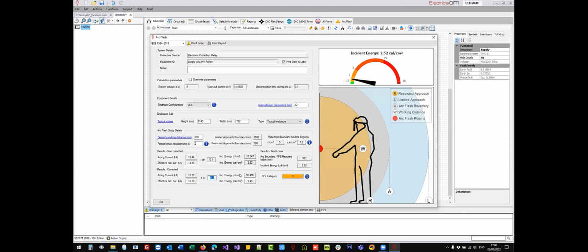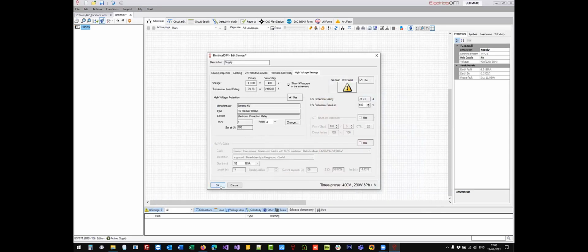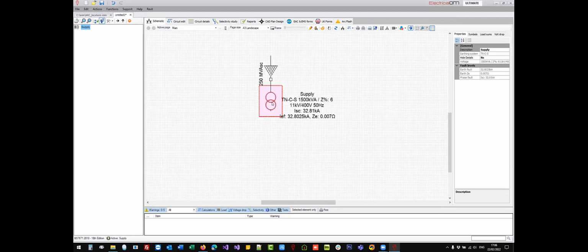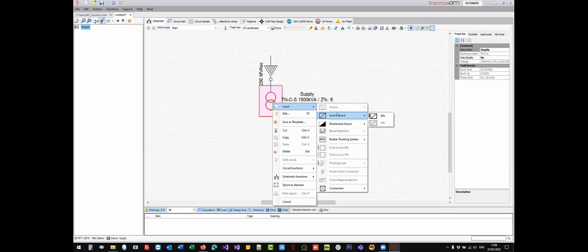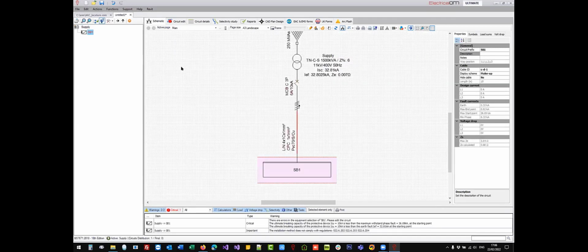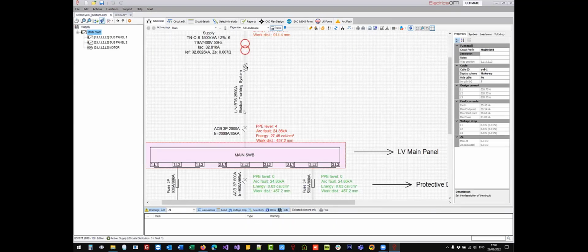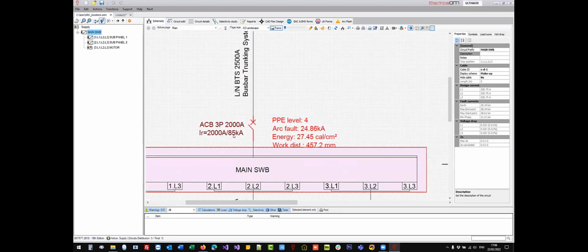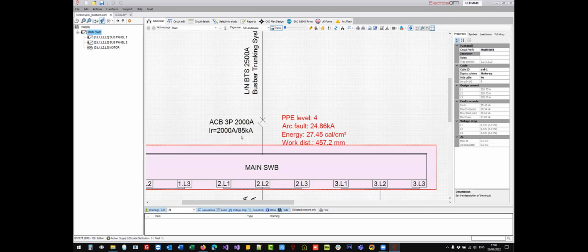Okay, so we can see that there is a direct link between the settings of the device and, of course, the result of the incident energy to be considered. Now, I will OK this to accept all these changes, and then I will move on to inserting my main panel. So I'm right-clicking the source, insert switchboard, 3-phase 1, and I will create a similar arrangement to what we see here. So we have a bus bar connecting the main switchboard, and at the incomer side we have an air circuit breaker at 2000 amps.